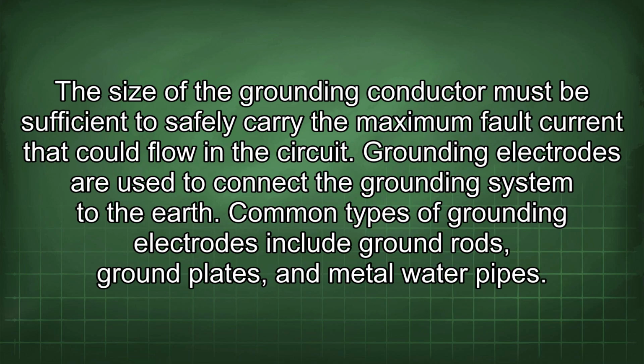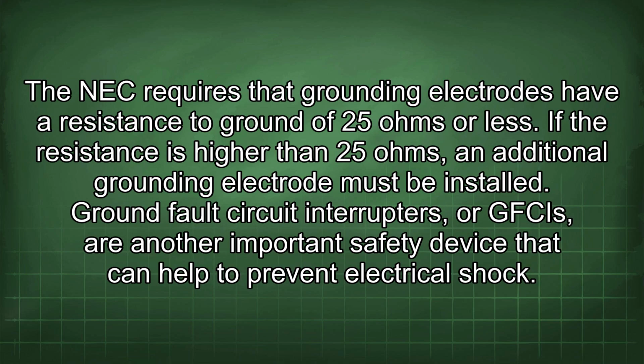The size of the grounding conductor must be sufficient to safely carry the maximum fault current that could flow in the circuit. Grounding electrodes are used to connect the grounding system to the earth. Common types of grounding electrodes include ground rods, ground plates, and metal water pipes. The NEC requires that grounding electrodes have a resistance to ground of 25 ohms or less. If the resistance is higher than 25 ohms, an additional grounding electrode must be installed.